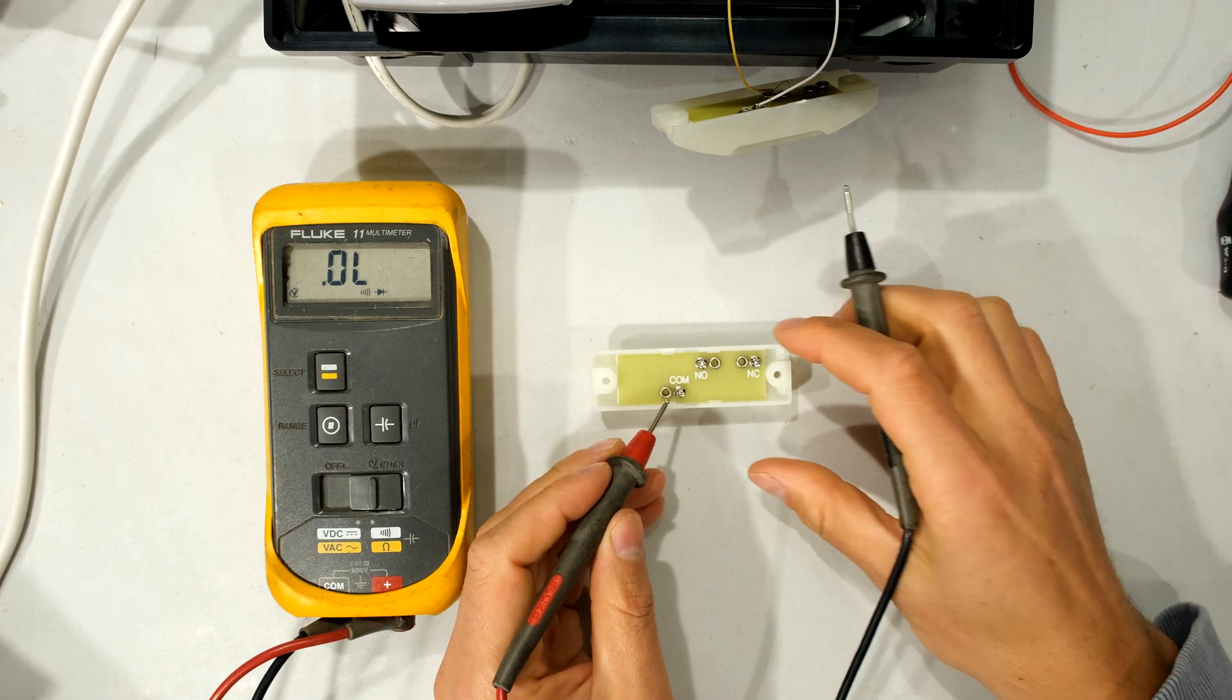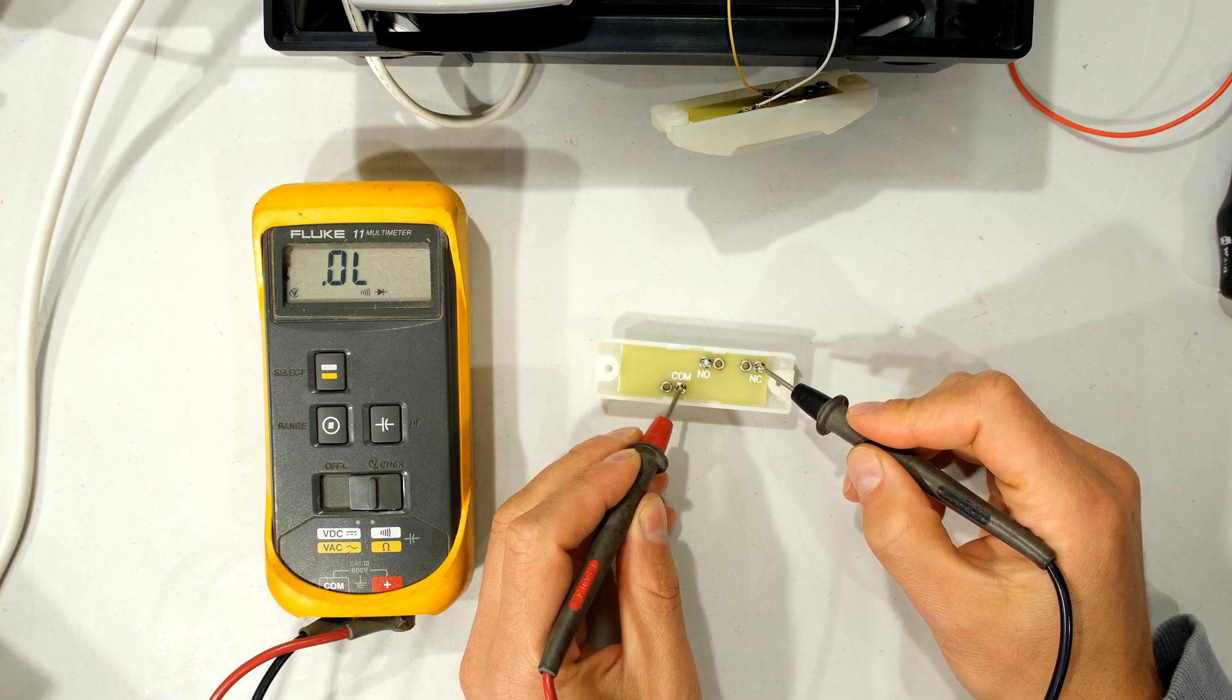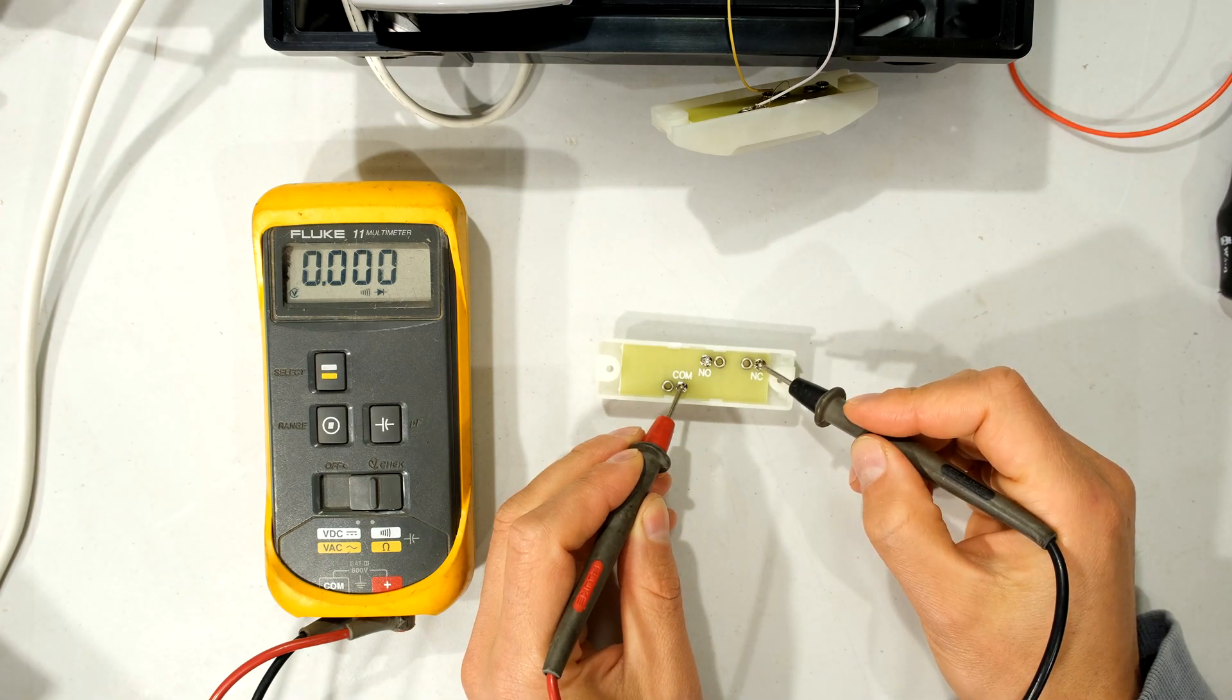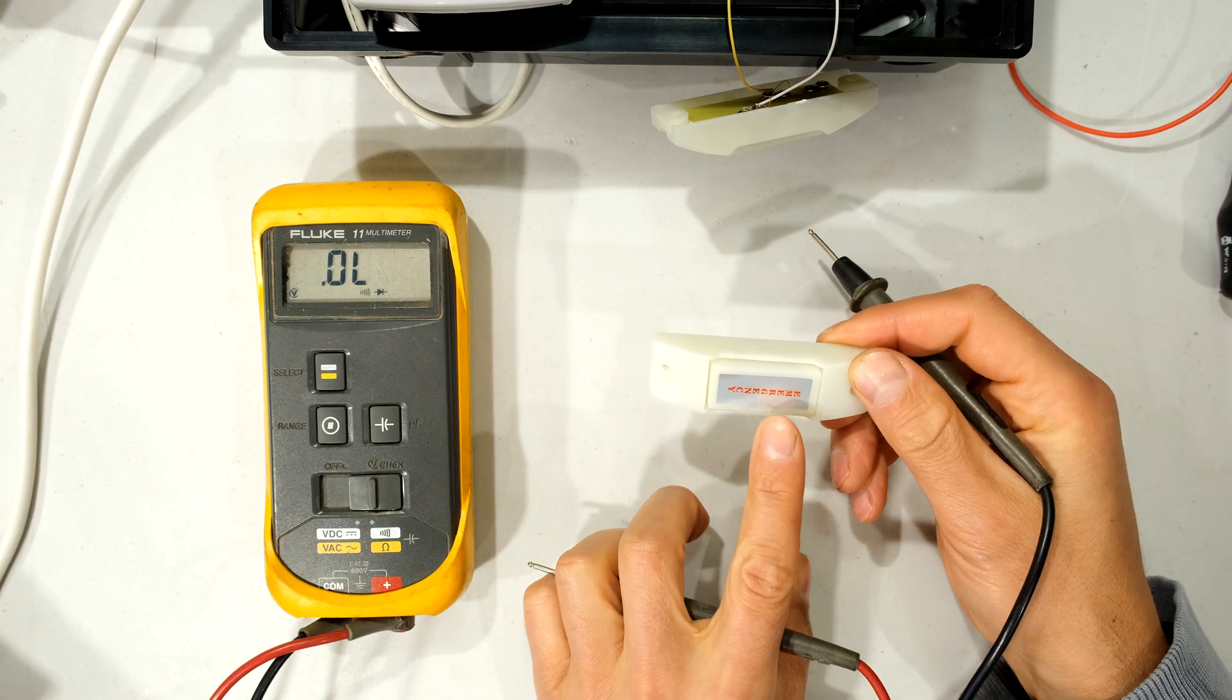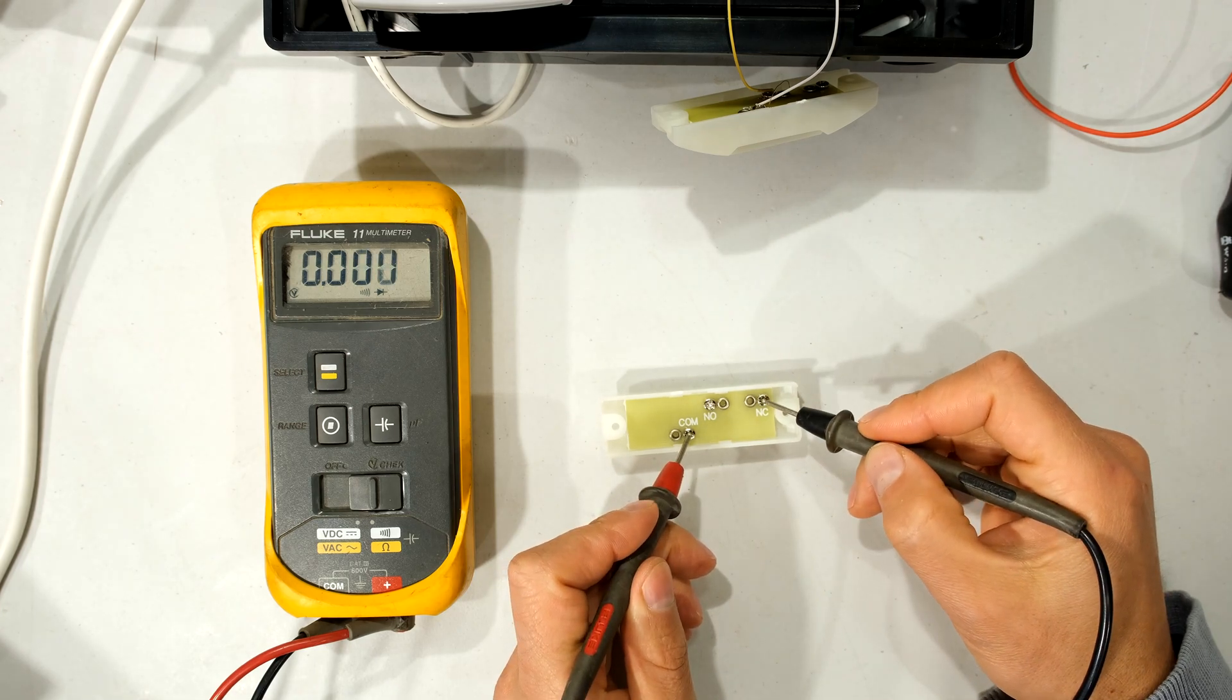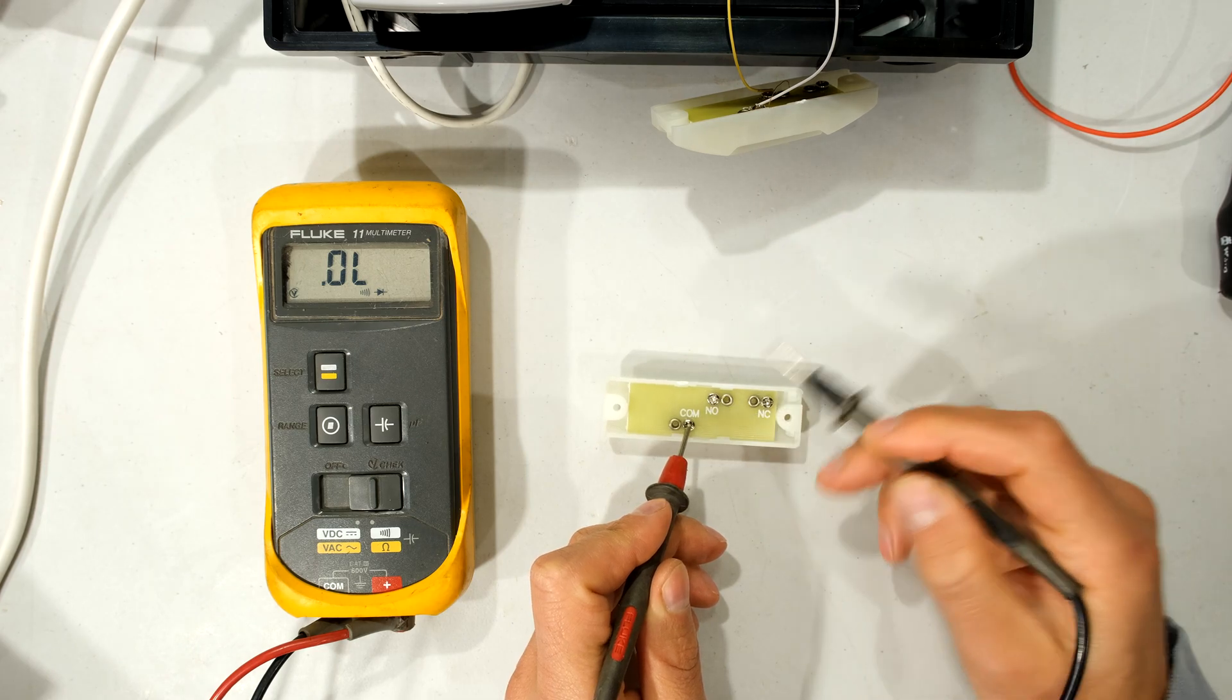When I put my lead on the common and I put my other lead on the NC listen to my meter and look at the display it will go to zero, telling me it's a short circuit. That means that this is a short circuit while the button is not depressed. You see I have not depressed the button and look at that, it's a short circuit. If I go to the NO option you can see it's an open circuit.